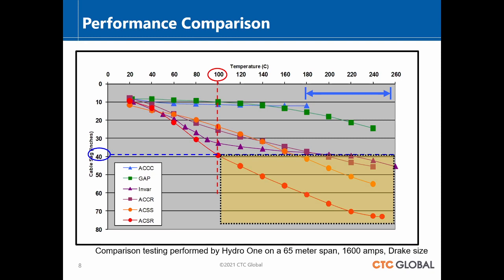The other point I want to show in this slide, the last point, is we commented that all of those endpoints are operating at the same current. We're going to call that current I, because the engineers call it I squared R. That's the heating that goes on in those lines when current flows through them. At the endpoint, they all have the same I. They all are operating at 1600 amps. 1600 squared is the same number for all of them. So they all differ only by resistance. If they run hotter, it just means that their resistance is higher in order to run out to that 1600 amps. And here you see the lowest temperature of all of those is the ACCC running at 180, the most efficient conductor of those that were sampled by Hydro One.